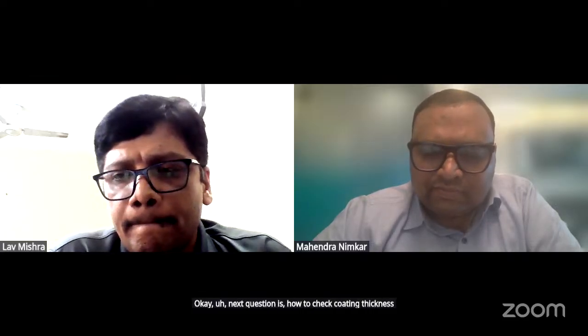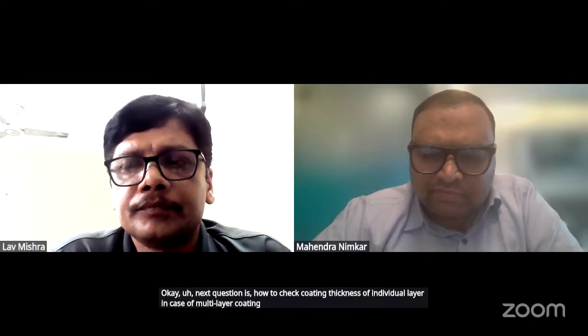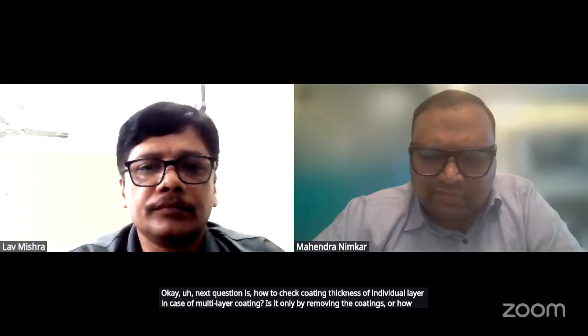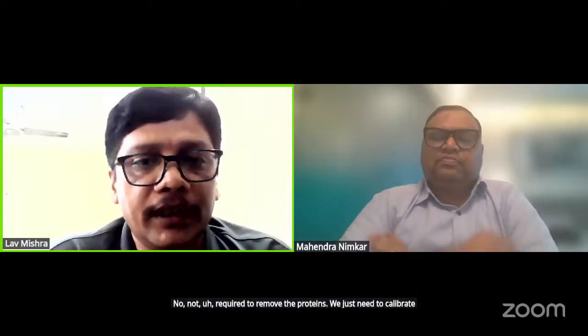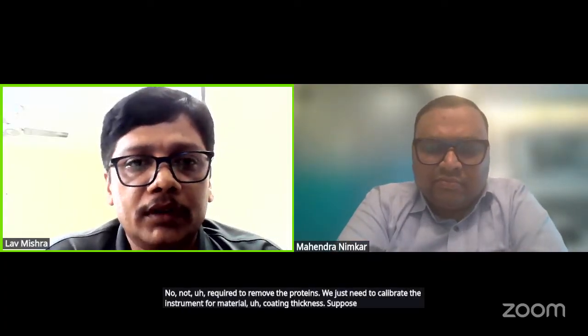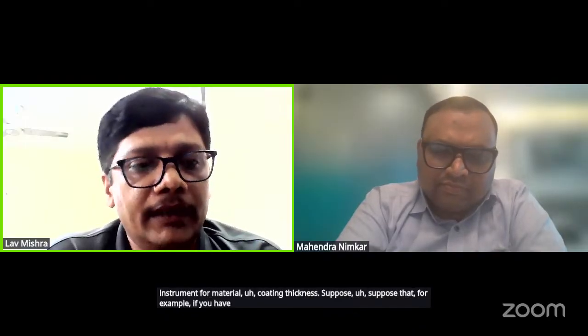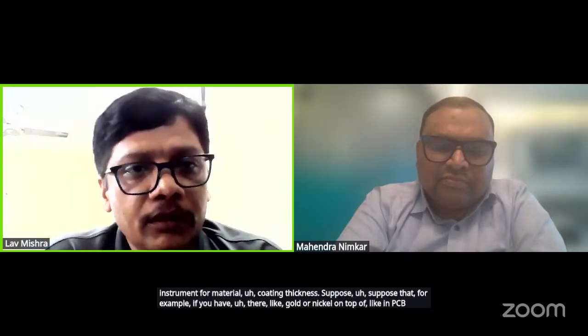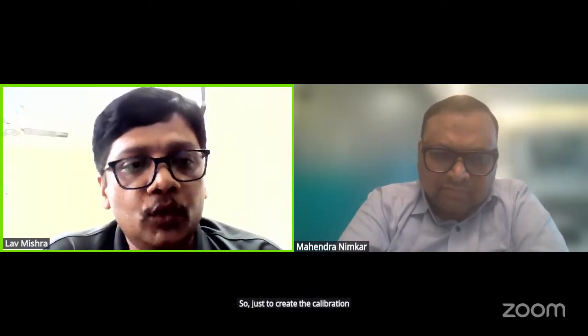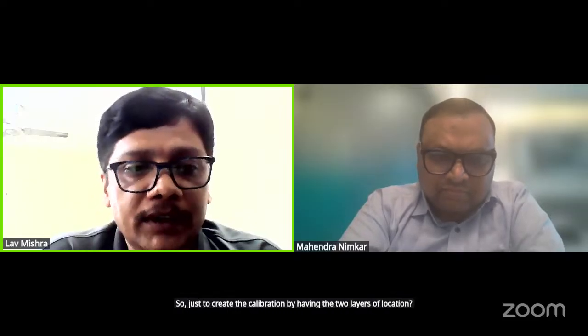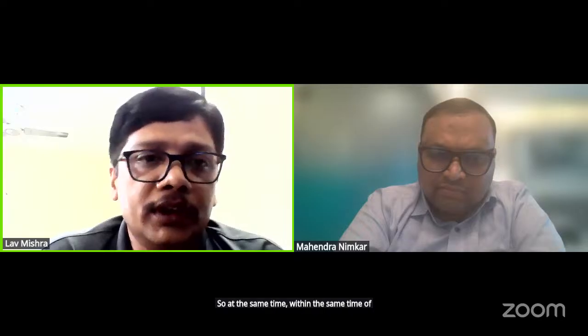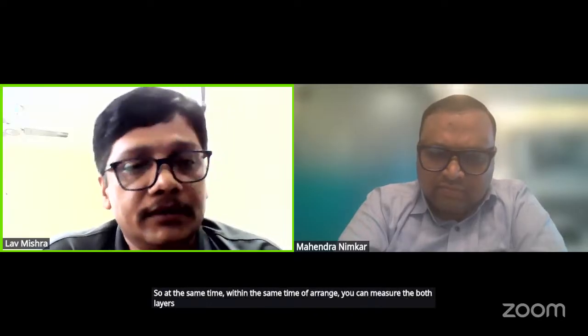Next question: how to check the coating thickness of individual layers in case of multi-layer coating? Is it only by removing the coatings? No, it is not required to remove the coatings. We just need to calibrate the instrument for multi-layer coating thickness. Suppose you have gold on nickel on copper, like in the PCB sector, we create a calibration for the two-layer application, so within the same time you can measure both layers simultaneously, without needing to remove the layers.